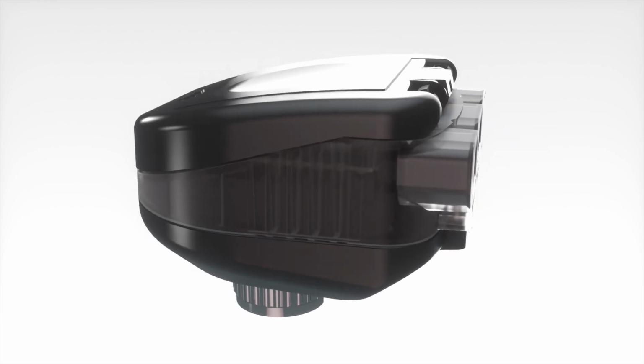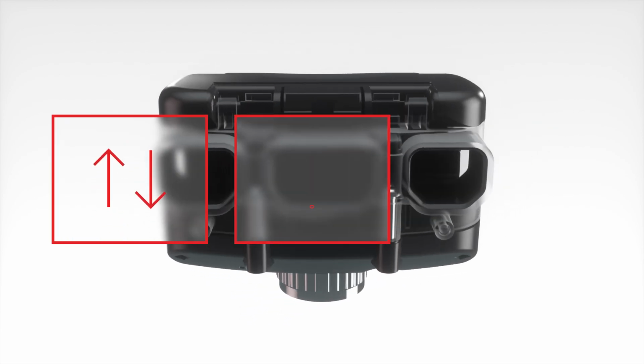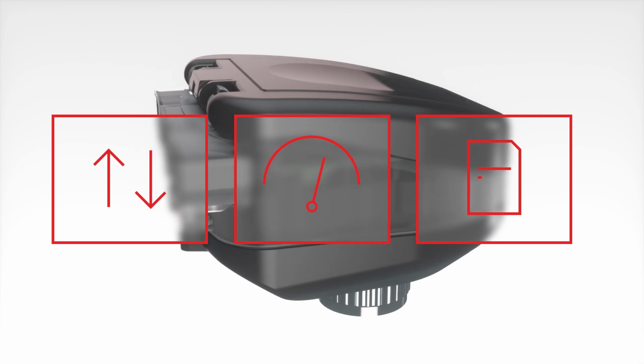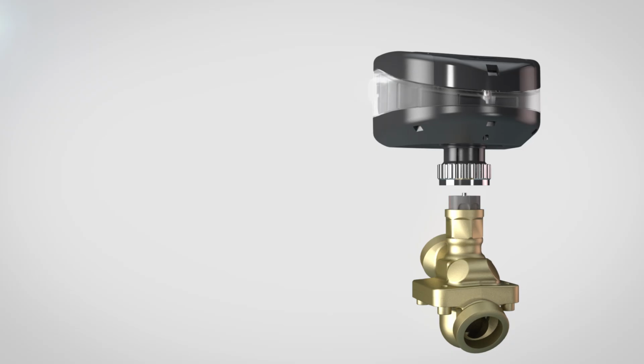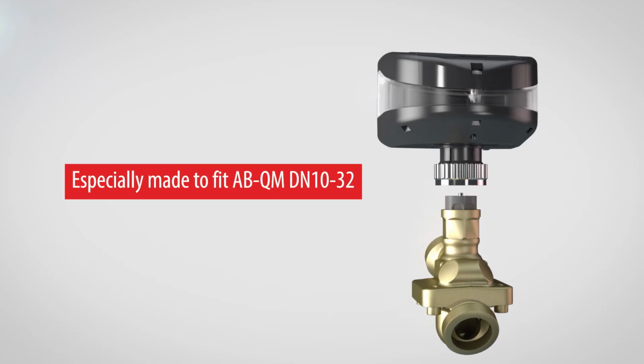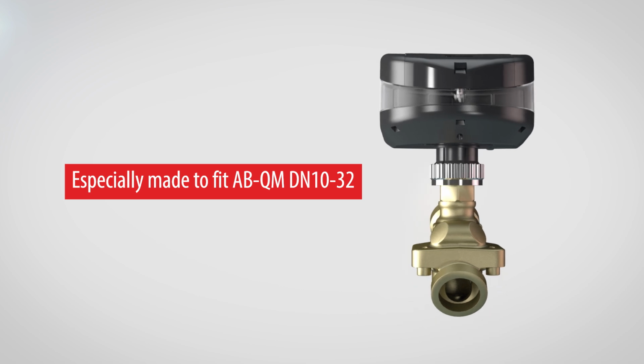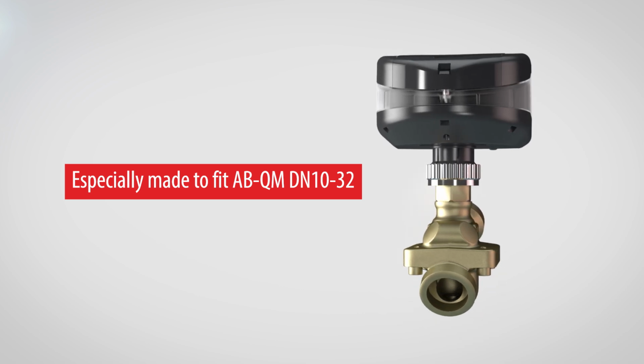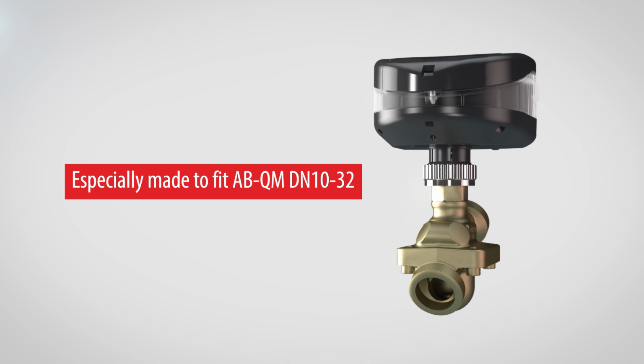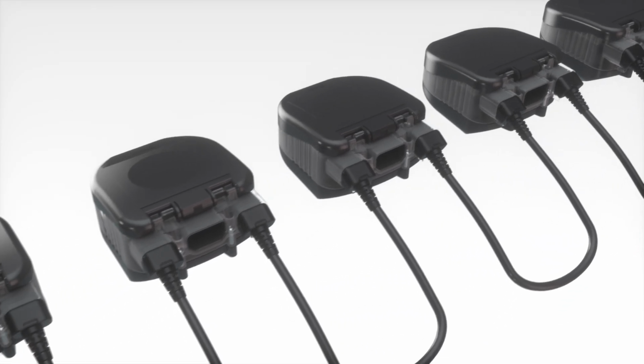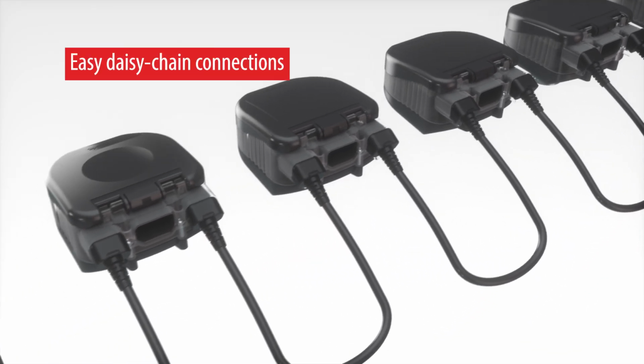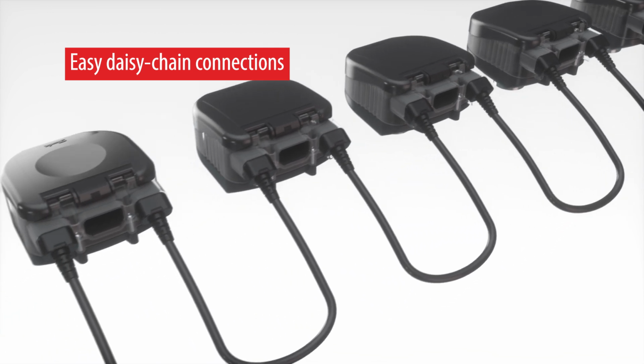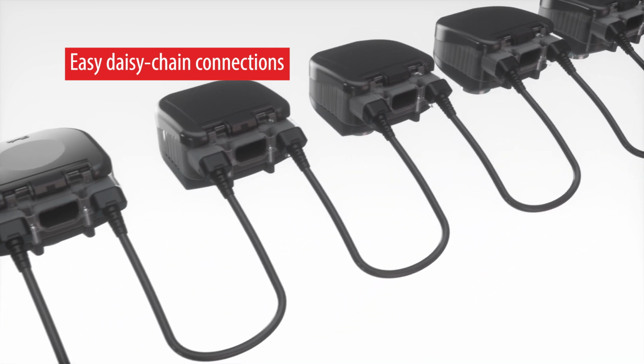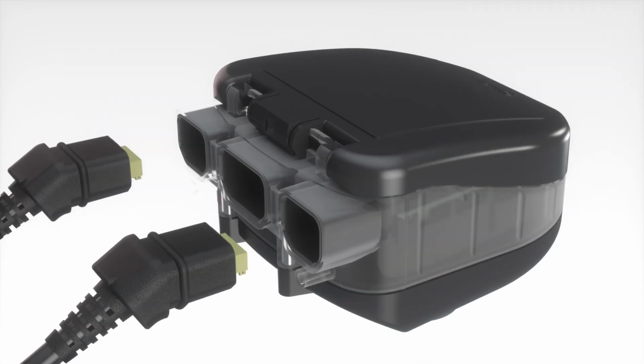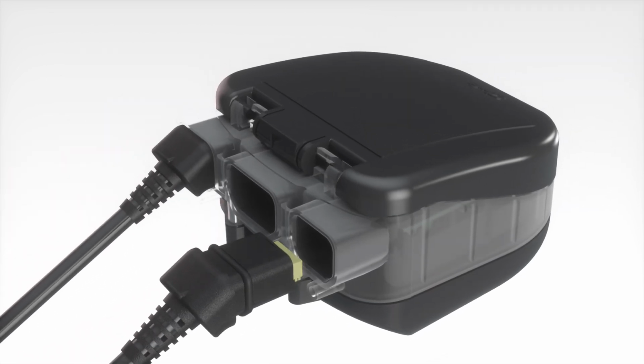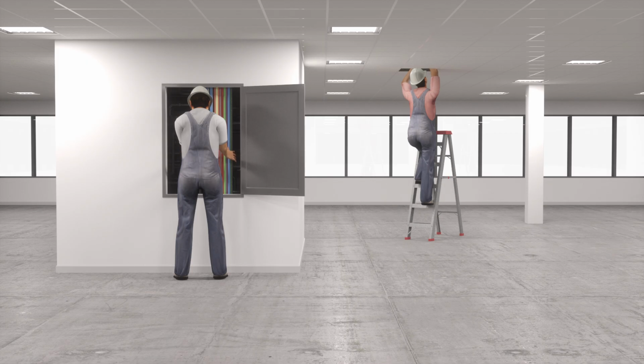The NovoCon actuator is a bus communication device, a flow indicator, and a data logger all in one. And it is designed to perfectly fit the Danfoss ABQM pressure independent balancing and control valve. Together, they are revolutionary. With NovoCon, all setting and control is possible via field bus and requires minimal data points. And NovoCon uses field bus cables with prefabricated plugs for daisy chain connection.